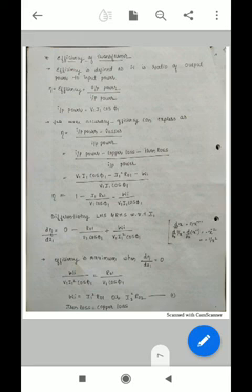So we are applying the input, but we don't know how much output we are getting at the output side of the transformer. So to measure with more accuracy, we go for one more efficiency formula, that is eta is equal to input power minus losses divided by input power. Next, the losses are of two types in a transformer: copper loss and iron loss. Next step, I substitute the formulas. Input power will be V1 I1 cos phi 1, copper loss is I1 square R01, and iron loss is written only as Wi. Next, dividing separately, then differentiating with respect to I1.